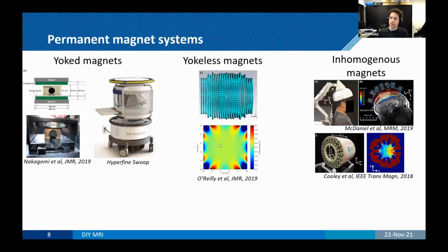The permanent magnet systems can then be subdivided into 3 different parts - or really 2.5, since the yokeless magnets and inhomogeneous magnets have a lot of overlap. I wanted to separate them because they conceptually work differently in MRI: the way they generate the magnetic field is the same, but the application is conceptually different. For the yoke magnets, they typically have some magnetic material at the bottom and at the top.